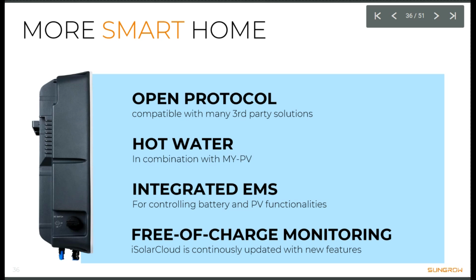So regarding this, of course, the inverter can achieve high self-consumption and grid independency, thanks to this optimized energy management system. Through the Modbus TCP/IP protocol, the EMS or control box from third-party devices can fully control the on and off of the system, can help regulate the charging and discharging of the inverter, or, for example, also clipping or derating the inverter in case that is needed. The EMS can of course also control the storage system to coordinate the frequency regulation as well.